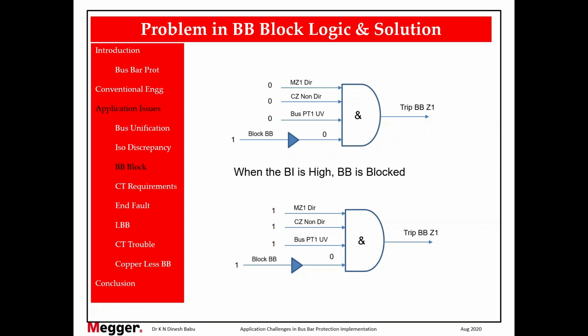Now why did this occur? When we analyzed it, we found that this binary input should become high to block bus bar, but before the binary input became high, the tripping was already executed, because when this input is low, this would be 0 and this would be 1, so it would allow tripping. Whenever there is a reboot of the relay, and a relay can reboot even if you write the settings. DC disturbance is one example. Even if you write 61850 settings, to implement that you have to reboot the relay. The moment you reboot, before your input senses, the bus bar will trip. So this is a dangerous scenario.